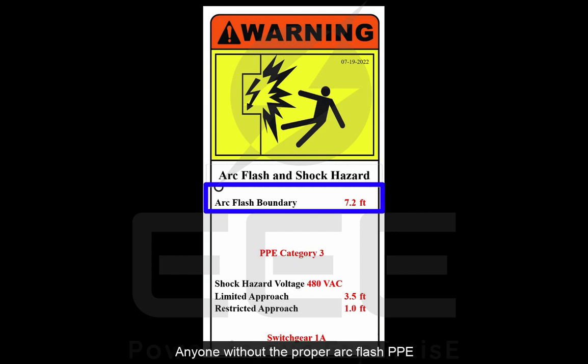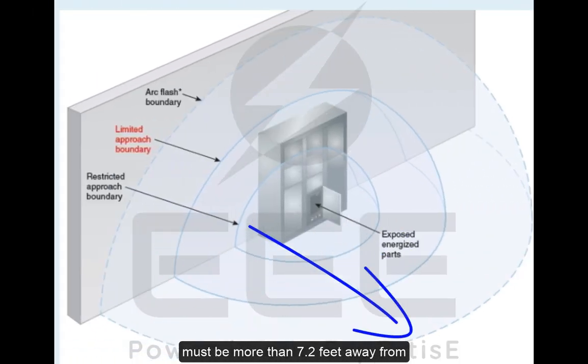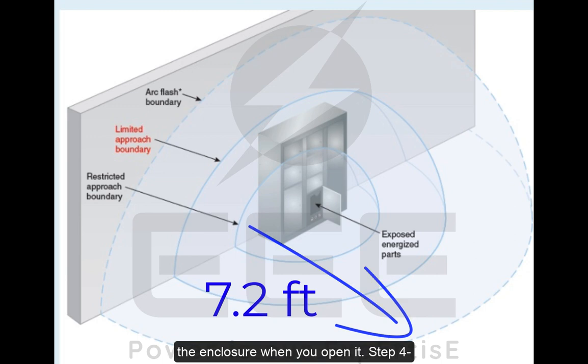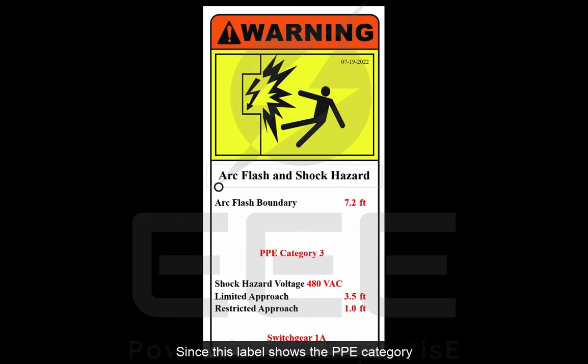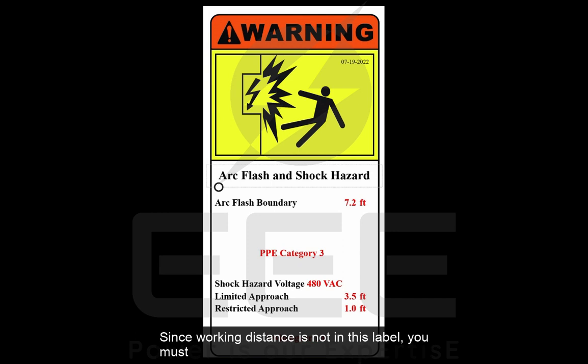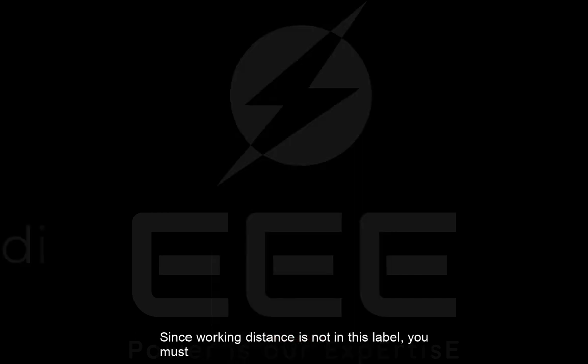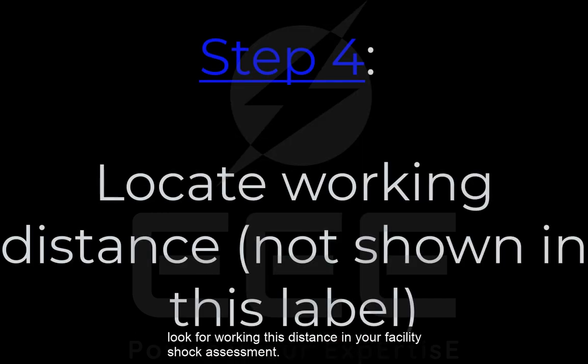Anyone without proper arc flash PPE must be more than 7.2 feet away from the enclosure when you open it. Step 4. Since this label shows the PPE category instead of incident energy, it is not required to have a working distance on the label. Since working distance is not on this label, you must look for working distance in your facility's arc flash assessment documentation.